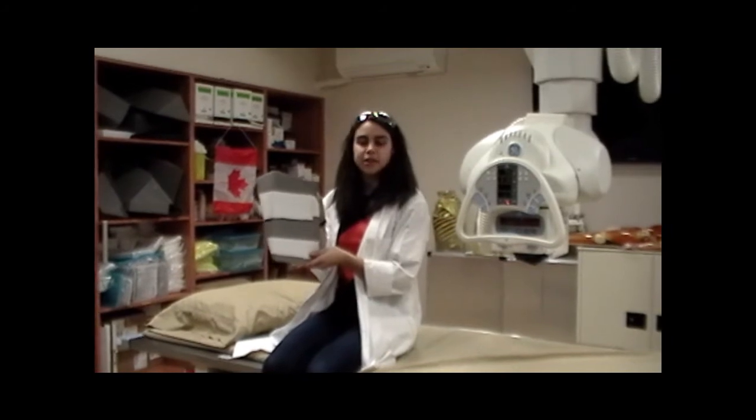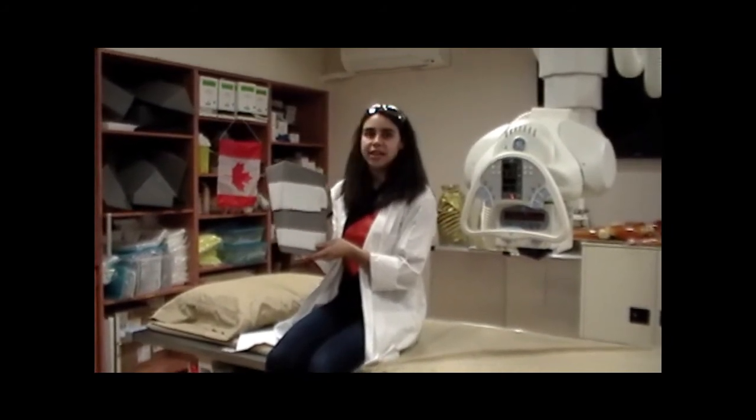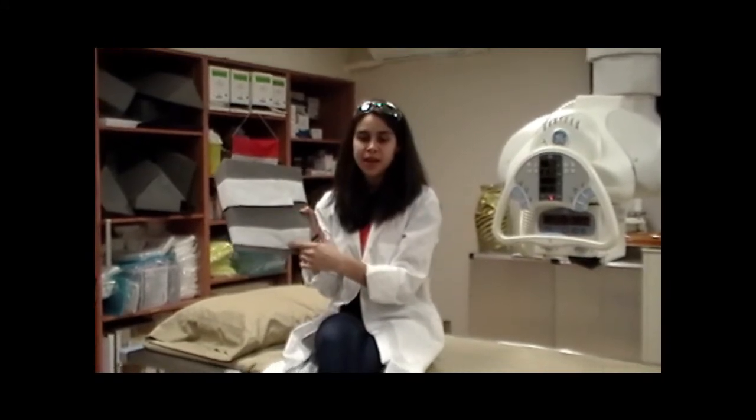This angling allows for good heat capacity and image quality. The smaller the focal spot size, the smaller the penumbra and better the image quality. But it can only withstand up to a certain limit of mA. Too much and you'll get pitting. To rectify this, you'll have a longer exposure time, or you'll have to use the larger focal spot.